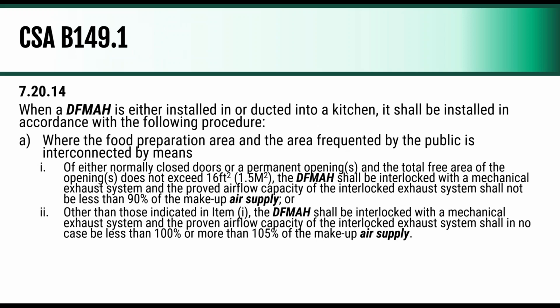So just looking specifically for direct fired makeup air units, this is from CSA B149, and it's when a direct fired makeup air is installed or ducted into a kitchen, it should be installed in accordance with the following procedure. So just based on us saying everything needs to be negative, but you don't want to be too negative, let's read these.